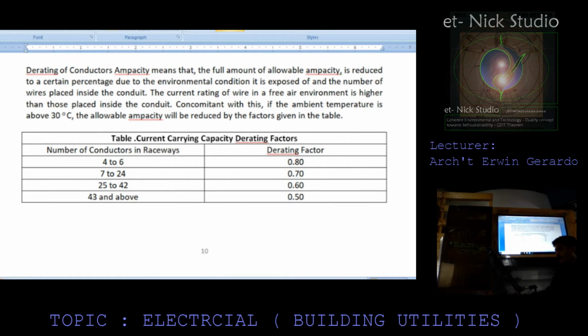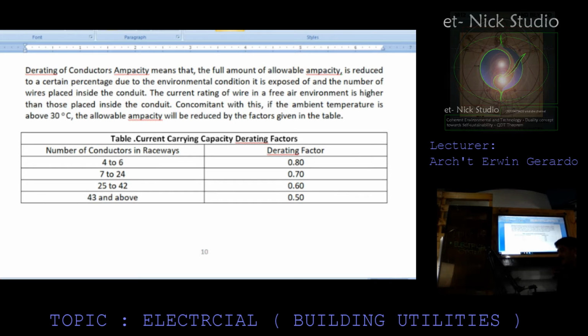The derating of conductor's ampacity means that the full amount of allowable ampacity is reduced to a certain percentage due to the environmental condition it is exposed to, and the number of wires placed inside the conduit. The current rating of wire in a free air environment is higher than those placed inside the conduit. Concomitant with this, if the ambient temperature is above 30 degrees, the allowable ampacity will be reduced by the factors given in this table. Current carrying capacity, the derating factors.